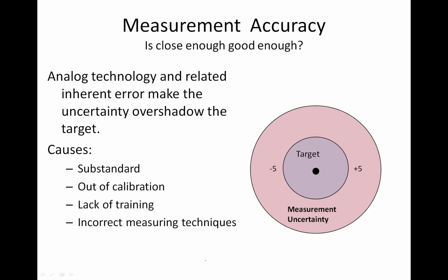Could be a lack of training. Simply, how do you attach that thermocouple to the pipe or the clamp to the pipe? Where do you attach that? Pipe diameter plays some things in with that. If we have a larger pipe diameter, we might want to be at the 4 o'clock position on the pipe. So we got to make sure that we understand where to make the measurement at, and simply incorrect measuring techniques.